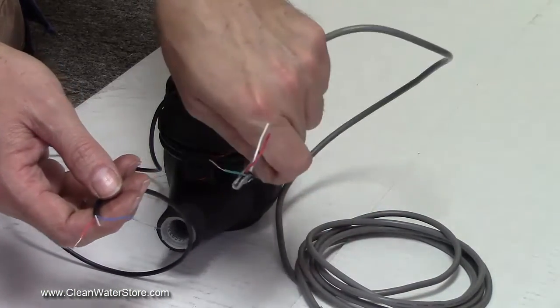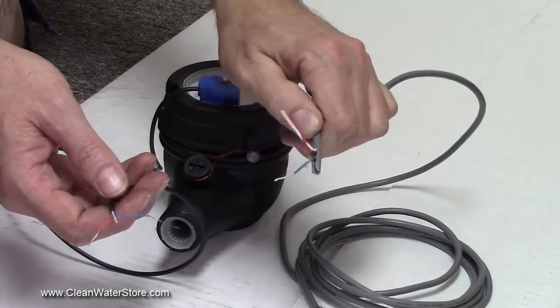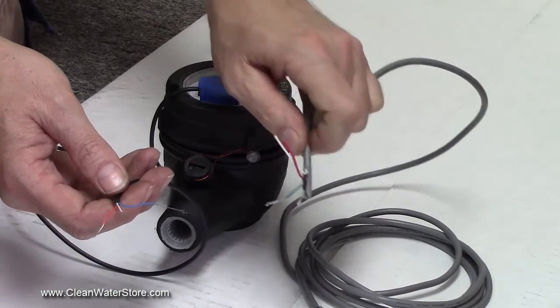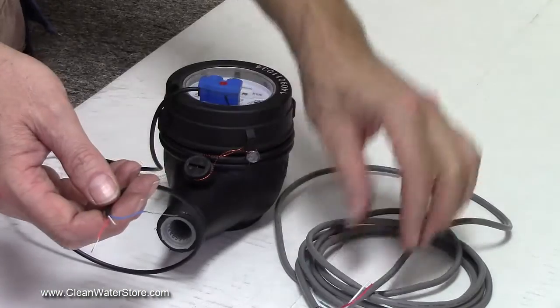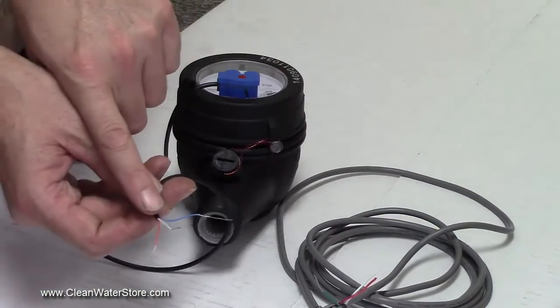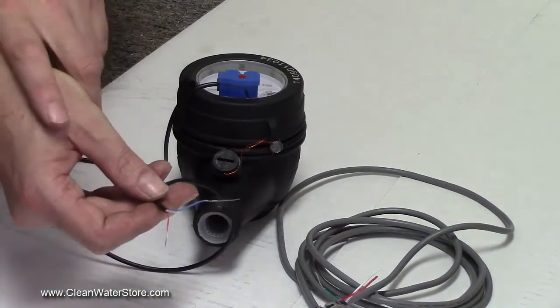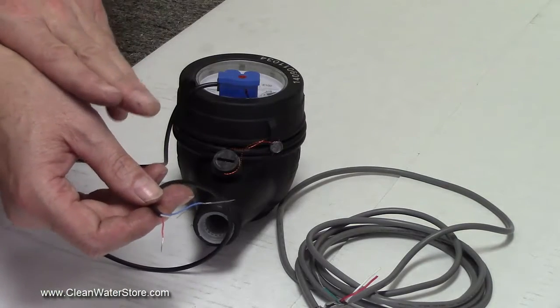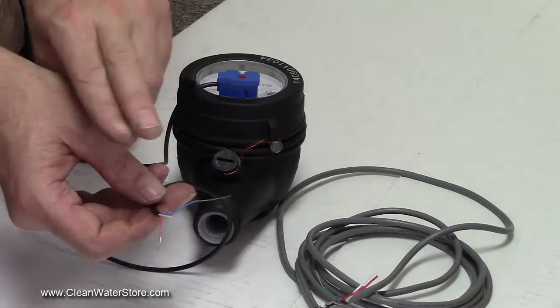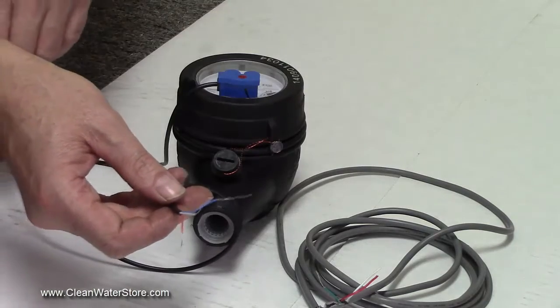The flow meter has three wires: red, white, and blue. In fact, we only need to connect two wires to two wires. The black wire on the meter cable that goes to the Precision 24 hooks up to the white wire, so black to white is the first connection.